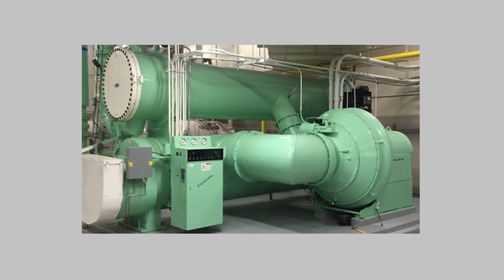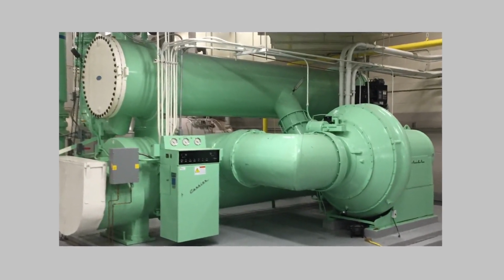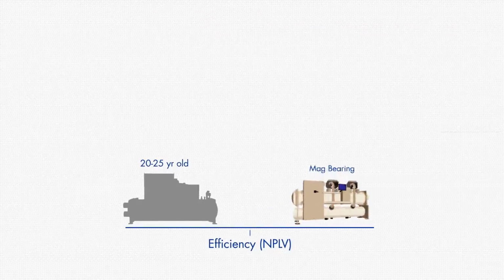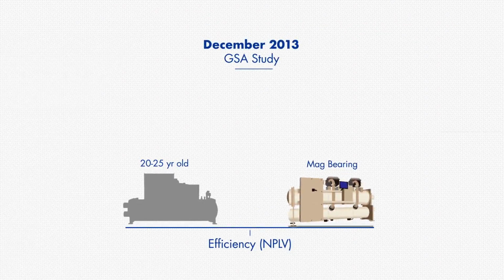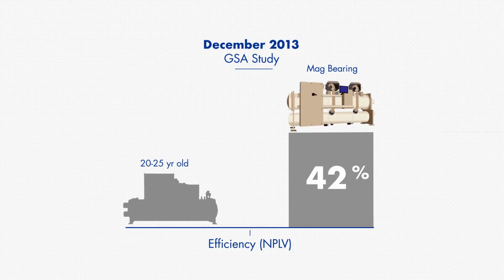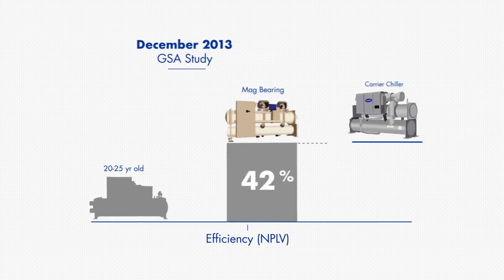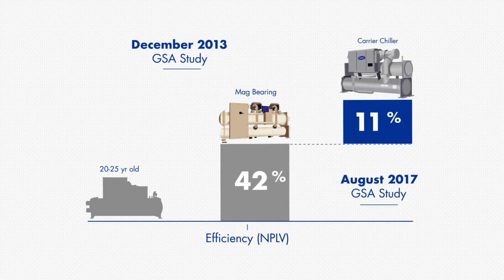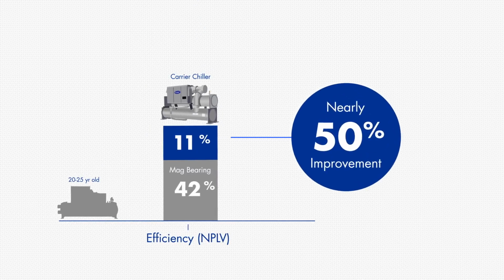The savings become even more impressive when you think about them in the context of your existing chiller plant. Here's what we mean. An earlier GSA study in 2013 showed mag-bearing chillers to be 42% more efficient than the old constant speed screw chillers. Add the 11% gain in efficiency reported in this study, and the Carrier chiller offers total improvement of nearly 50% versus a chiller nearing the end of its useful life.